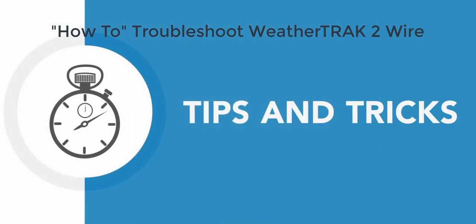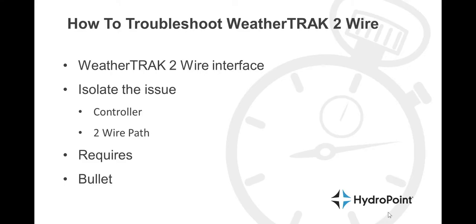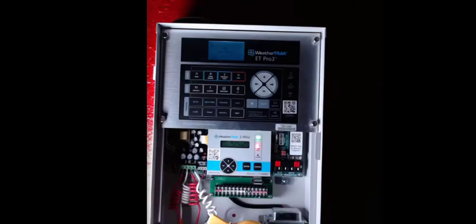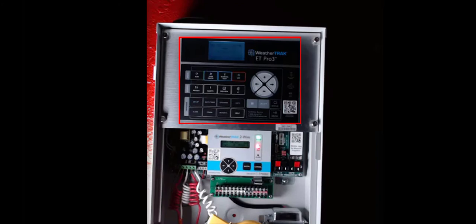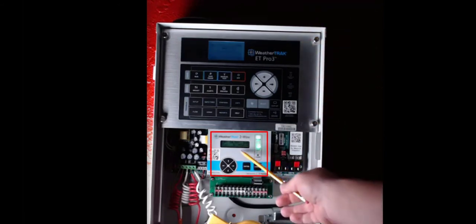How to Troubleshoot WeatherTRAK 2-Wire. The first step in troubleshooting the WeatherTRAK 2-Wire is being able to identify when you have a 2-Wire issue. To do this we need to first disqualify any WeatherTRAK controller issues. The WeatherTRAK interface manages many things including all the scheduling information and other WeatherTRAK feature specific information. So if there is an issue, the first thing to do is identify where the issue lies — is it a WeatherTRAK issue you can see online, or does it use our 2-Wire specific interface?